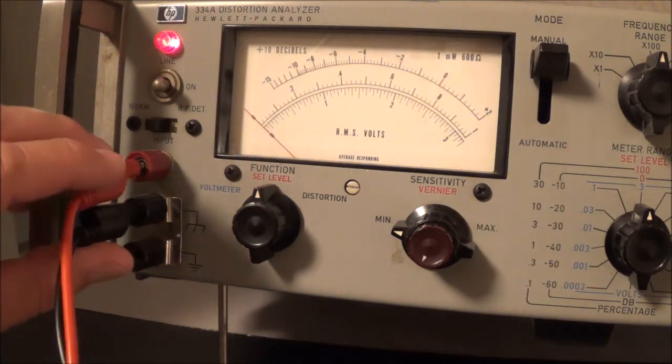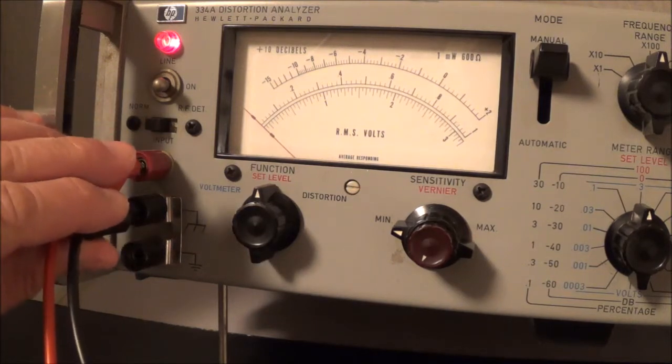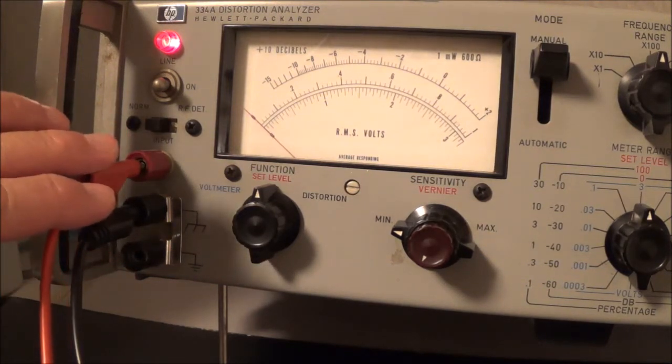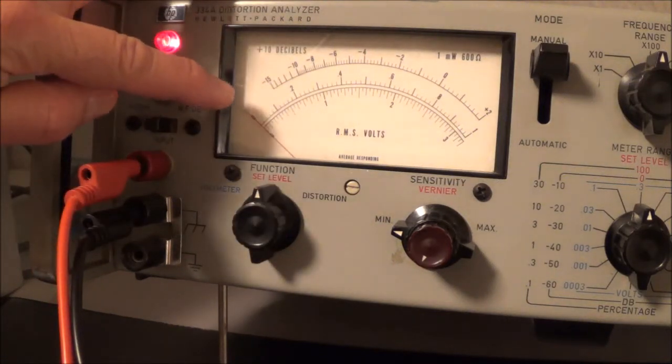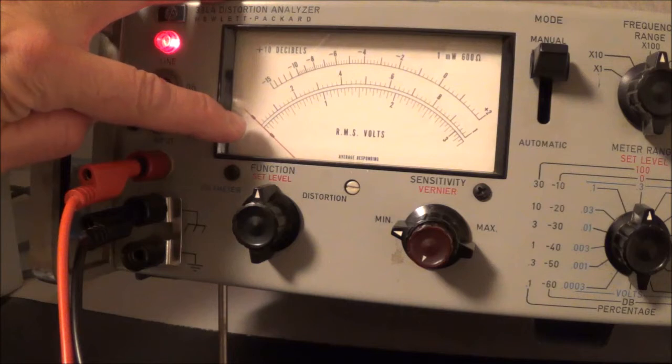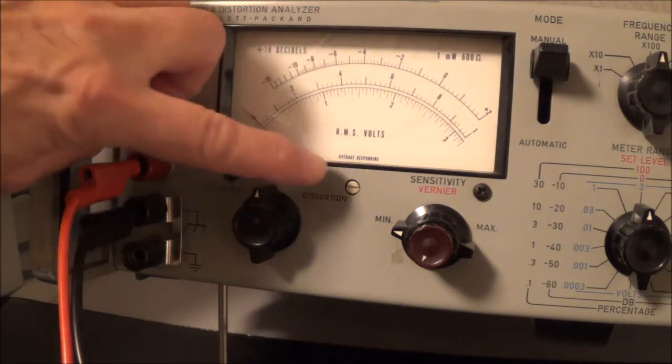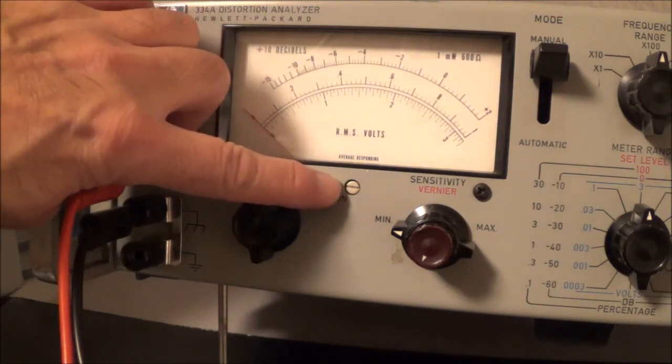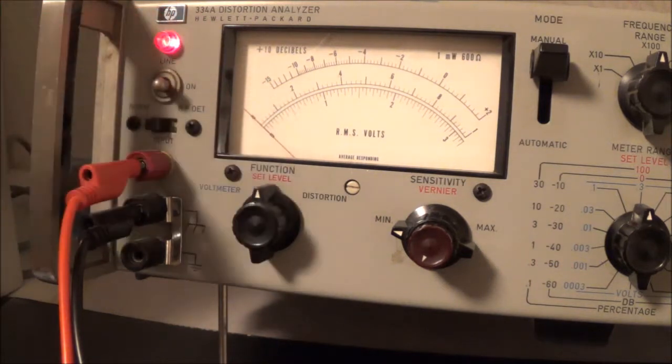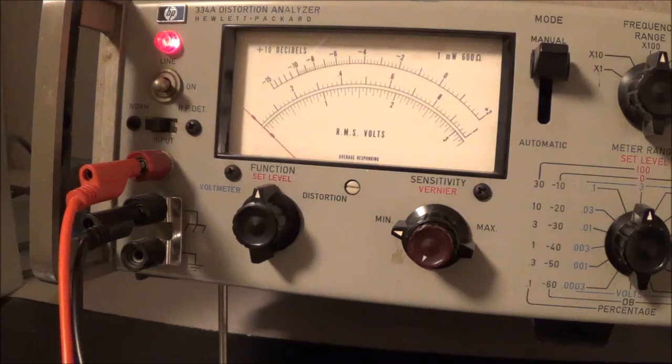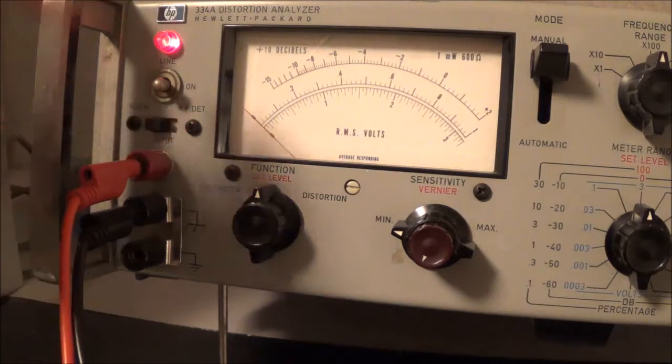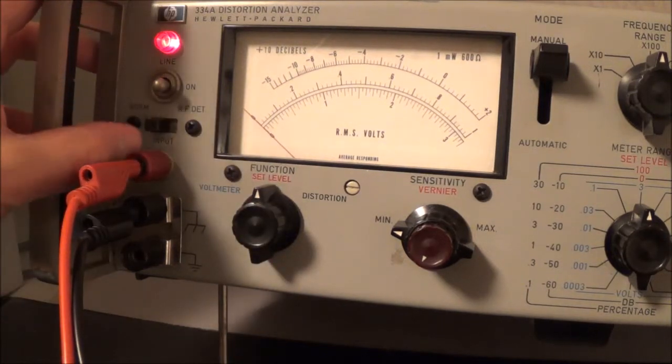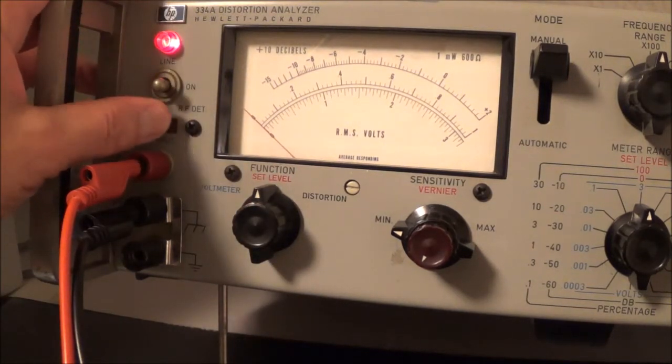And here you can see I've got the banana plugs hooked up here as the input. And the first thing I have to do, according to the manual, is make sure that this meter here is mechanically zeroed. If not, I think this is here for making sure that basically zeroes out. And then we're supposed to set the switch here to normal RF detection. That's supposed to be to the normal side.